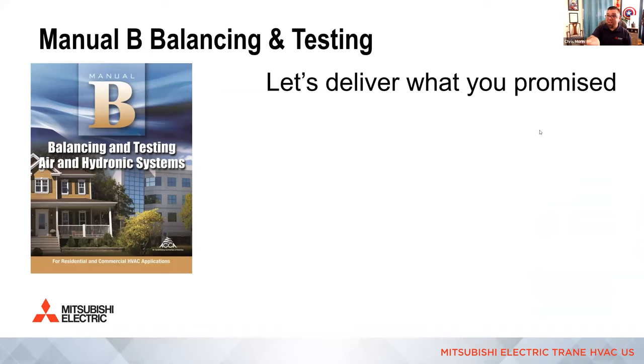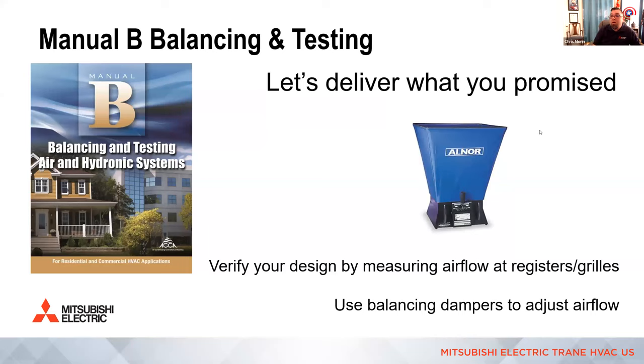All right. Now, of course, balancing dampers, a perfect follow-up to what Lee had mentioned. You have to deliver what you wanted to deliver to each room, right? Not just the initial trunk. You need to make sure you're actually balancing the system to get the full volume of air to each space. Otherwise, you're going to have uncomfortable rooms. A lot of people avoid this or don't do it correctly in residential applications. There's actually a balancing and testing manual. It's Manual B, and that would be the last piece. It's part of design and verification. Of course, you would need balancing dampers in there in order to adjust airflow. There are about three different ways to balance a system correctly, and Manual B walks you through each one. And if you're doing hydronic systems, it walks you through that as well.